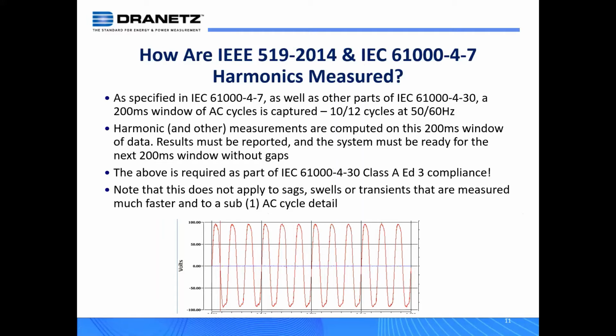So as specified in 61000-4-7, you measure a 200 millisecond window, and that's what's shown at the bottom over here. That represents 12 AC cycles at 60 hertz and 10 AC cycles at 50 hertz. And the harmonics, and in fact other measurements, are computed on this 200 millisecond window. So the instrument doesn't look at one cycle, it looks at either 10 or 12 cycles, depending if you're operating at 50 or 60 hertz, okay? And the above is part of IEC 61000-4-30, Class A Edition 3. So it's been part of the standard for a while. We're not focusing on that standard, but it's all wrapped together.